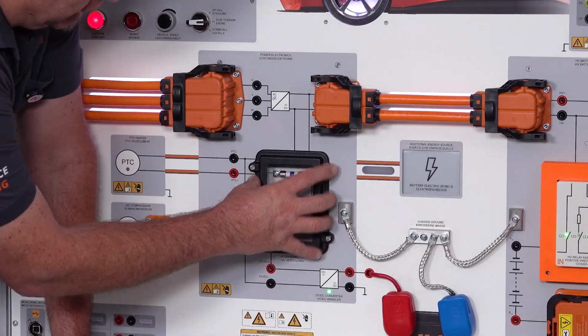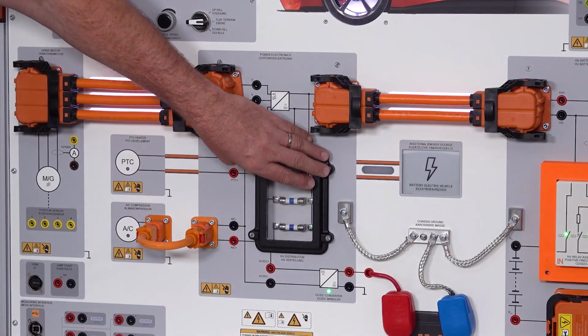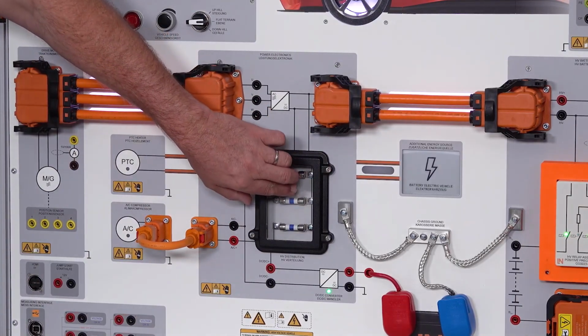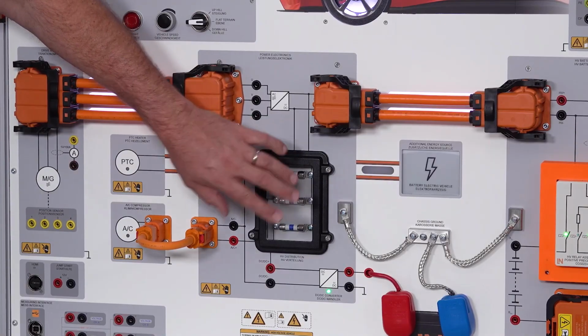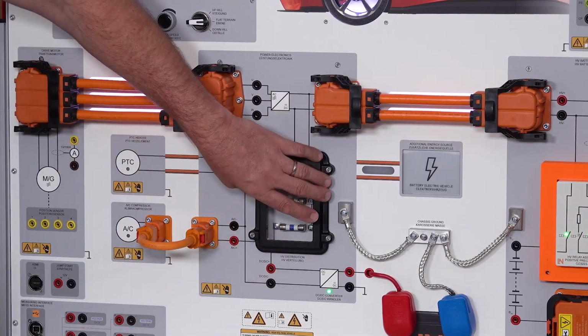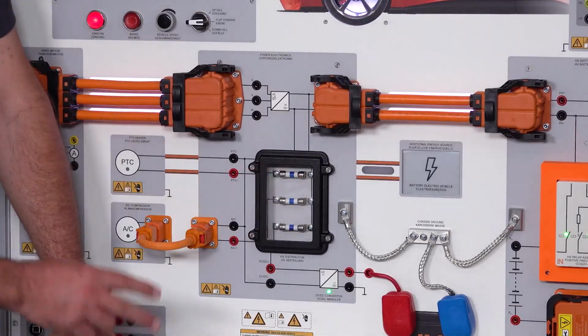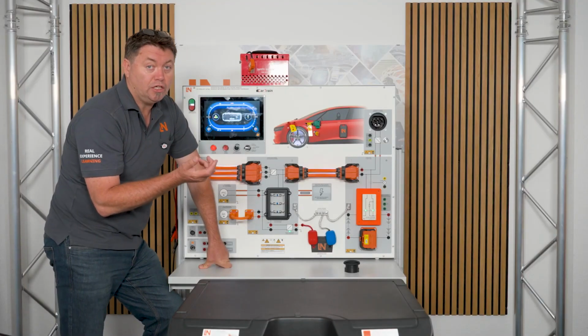This system, this cover here, has a double purpose. Underneath here is our high voltage inspection point. So when you're doing an isolation, a shutdown of the system, there's 2 points up here that you need to measure as a part of the live dead live testing.